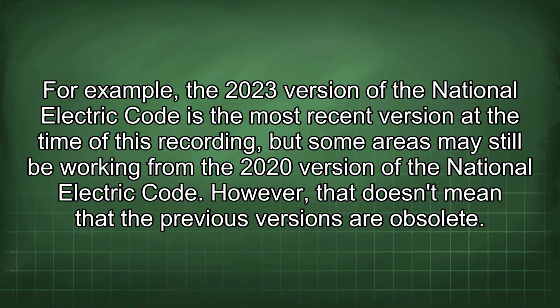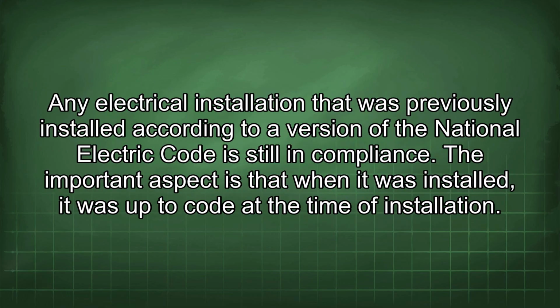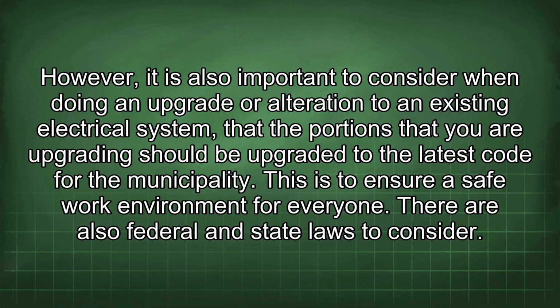However, that doesn't mean that the previous versions are obsolete. Any electrical installation that was previously installed according to a version of the National Electric Code is still in compliance. The important aspect is that when it was installed, it was up to code at the time of installation. However, it is also important to consider when doing an upgrade or alteration to an existing electrical system that the portions that you are upgrading should be upgraded to the latest code for the municipality. This is to ensure a safe work environment for everyone.